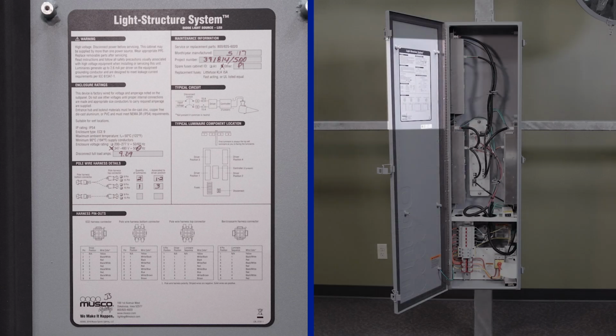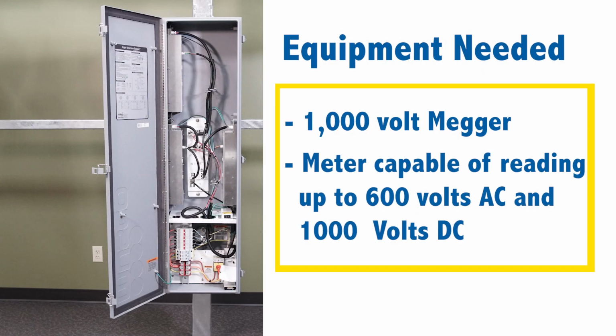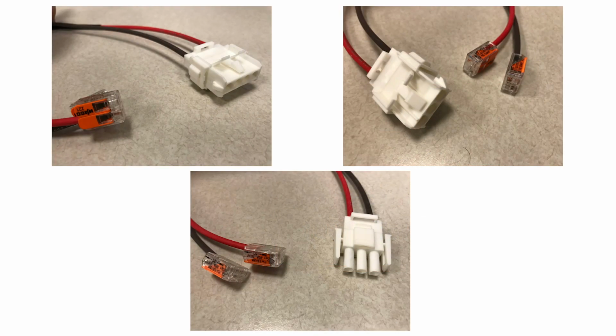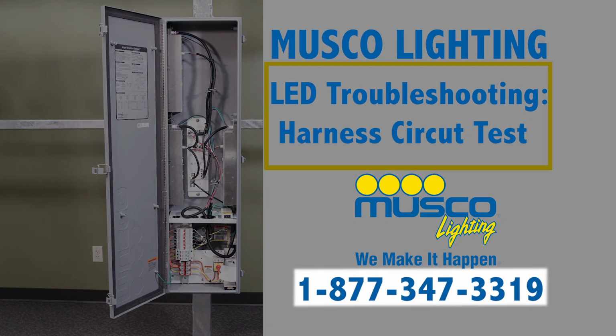For a complete troubleshoot, you will need the following equipment: a 1000 volt DC megger, and a meter capable of reading up to 600 volts AC and 1000 volts DC. In some circumstances, you may need MUSCO testing harnesses. Next, call MUSCO Control Link Center at 877-347-3319 and ask for technical support.